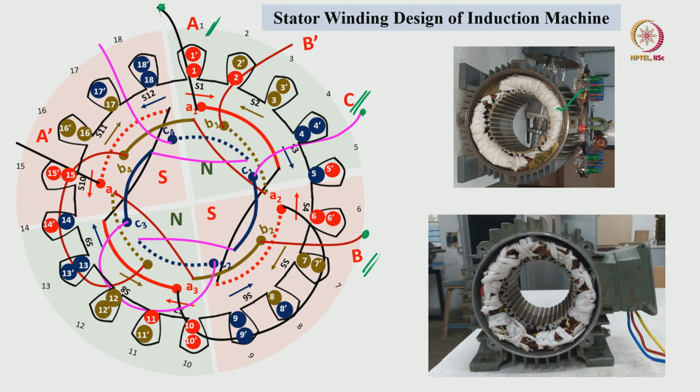Before doing the varnishing and threading, we have to verify the coil placements by utilizing the right hand thumb rule, and current excitation should be 120 degree displaced. Consider any instant, let us say A is positive current, B phase having the positive current, C phase having the negative current. So, with respect to this instant, whether 4 poles are forming symmetrically or not, we have to verify.